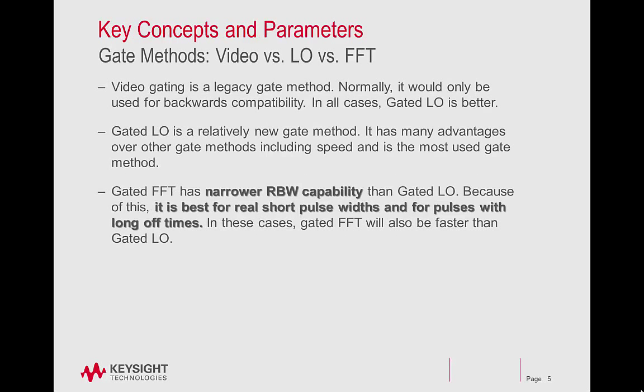Gate Methods: Video vs. LO vs. FFT. Video gating is a legacy gate method. Normally, it would only be used for backwards compatibility. For example, if you wrote some code around one of the older analyzers using video gating, then you may want to use video gating on the X-Series analyzer. In all cases, gated LO is better.